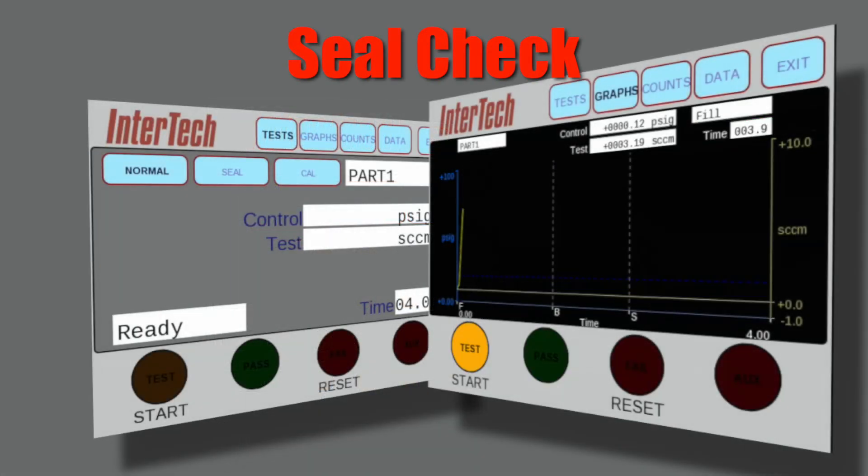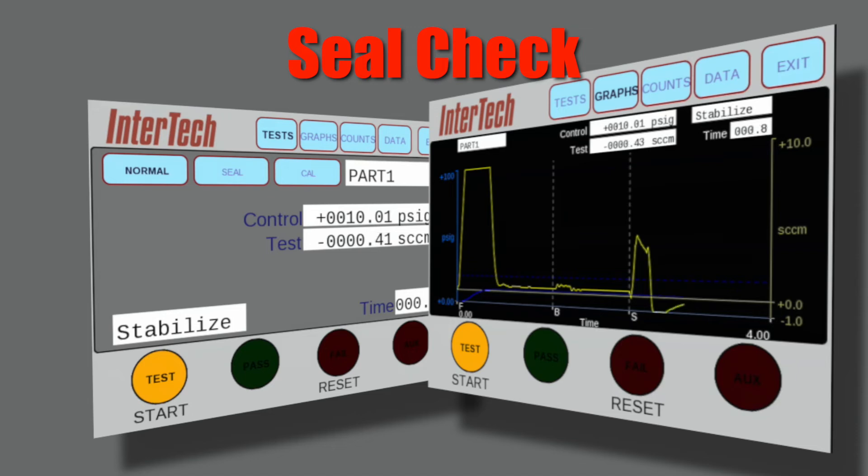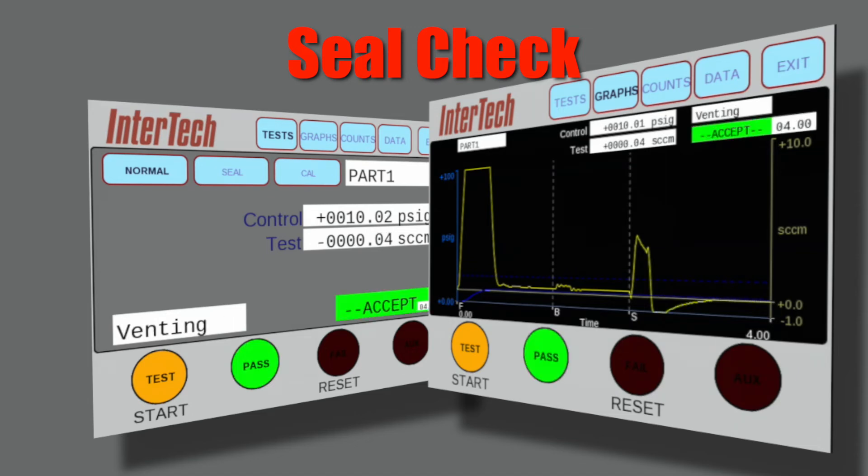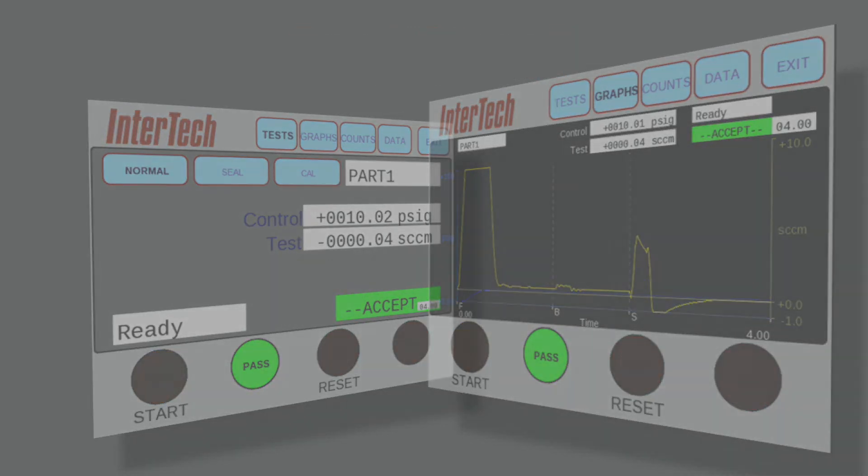Troubleshooting features on the M1075 include seal check mode which, when selected, runs the test through a normal test cycle but does not stop the test, instead maintains the test pressure on the test circuit and allows the user to inspect the system while under pressure.